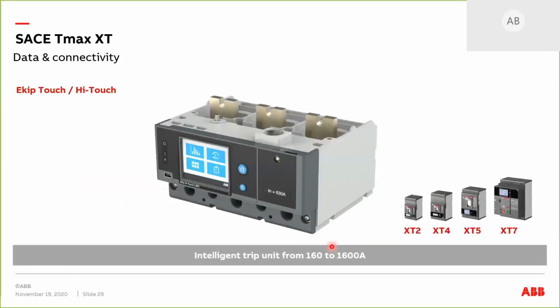So this is the touch and high touch that I'm talking about. This is an intelligent trip unit from 160 amps to 1,600 amps for the MCCB. But if we look at the ACBs we had, the range is actually from 160 ampere to 6,300 ampere, because they share the same technology. So whatever the ACB from the previous slide is capable of doing, the MCCB is also capable of doing.